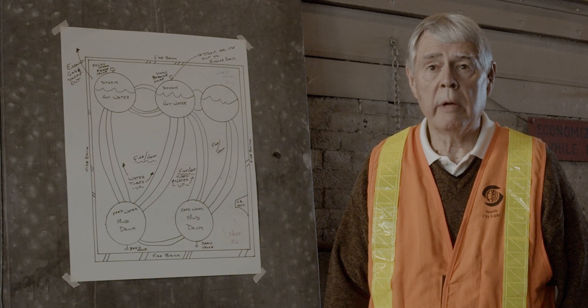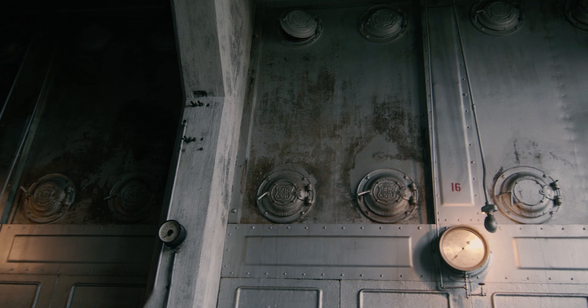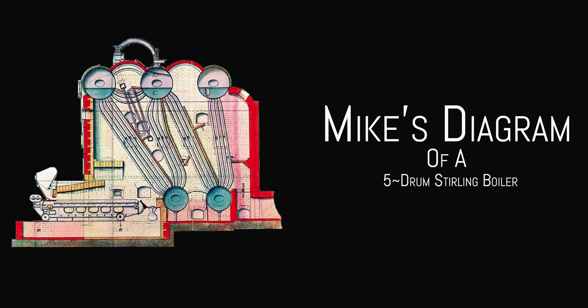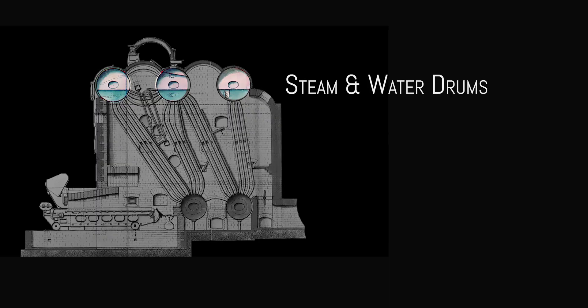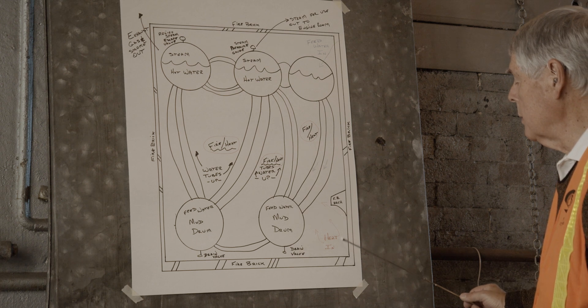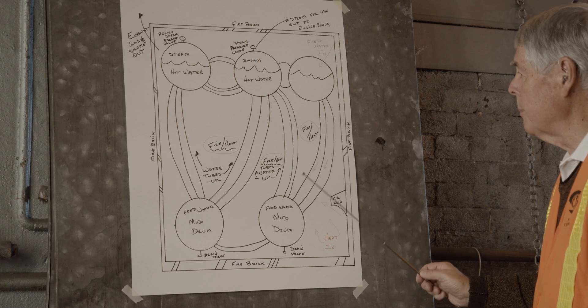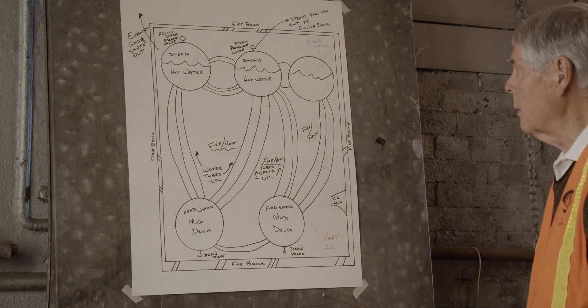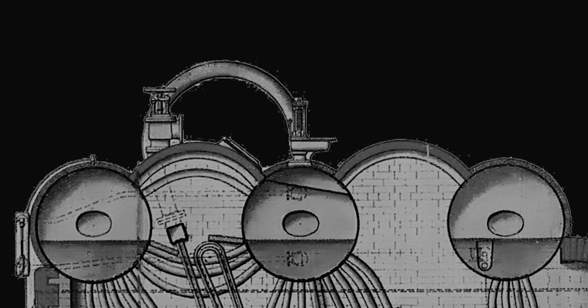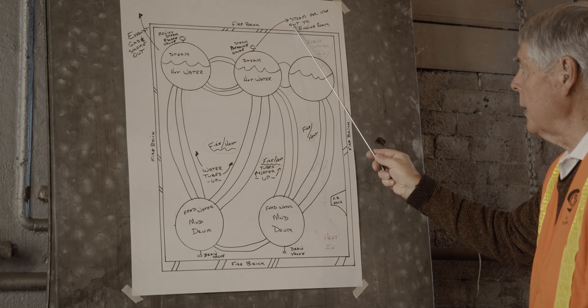This is a diagram of just a simple water tube boiler, of which we have 16 here, built in pairs. Feed water comes in from above into a drum. It flows down through three-inch diameter tubes into the two feed water or mud drums. The heat comes in from one corner and flows up through the entire structure, exiting in the upper left-hand corner. Steam and water drums collect the hot water as it rises and vent it off to the engine room for use.